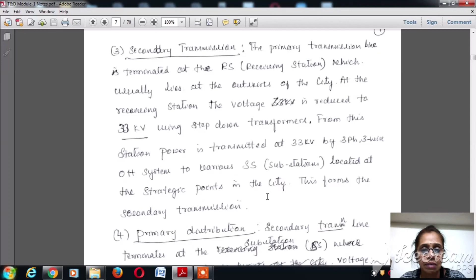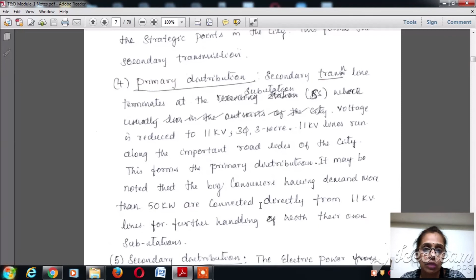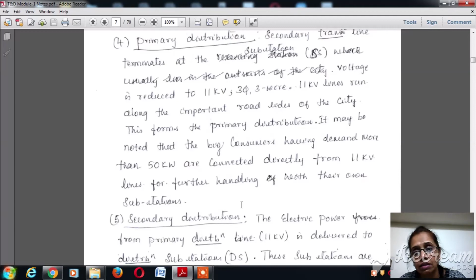Now thinking about the primary distribution, the secondary transmission line terminates at the substation, that is SS, as shown in the schematic diagram, and the voltage is reduced to 11 kV, three-phase, three-wire. 11 kV lines run along the important roadsides of the city, and this forms the primary distribution. It may be noted that big consumers having a demand of more than 50 kilowatts are connected directly to the 11 kV lines. These lines are called feeders, and the consumers will have their own substation wherein they utilize this 11 kV line.